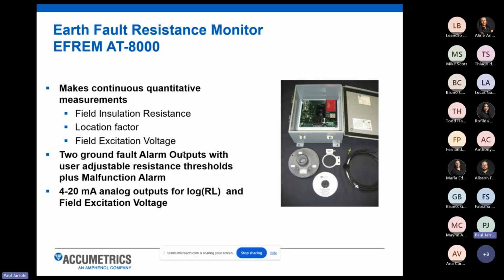And then lastly, we have another relay that's called our malfunction alarm. This will trigger if there's an issue with the telemetry system. So if the telemetry system ever loses power, or there's misalignment between the rotor and stator components, or the cable gets damaged or disconnected in any way, that will trigger a malfunction alarm, allowing the user to know that they're not being monitored and there's an issue with the telemetry system itself.